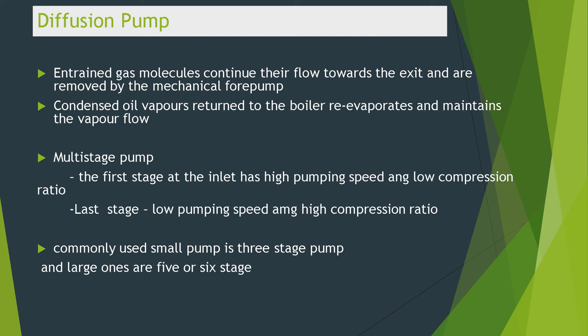In multi-stage pumps, the first stage at the inlet has high pumping speed and low compression ratio, while the last stage has low pumping speed and high compression ratio. The commonly used small pump is a three-stage pump, and the large ones are five or six stage.